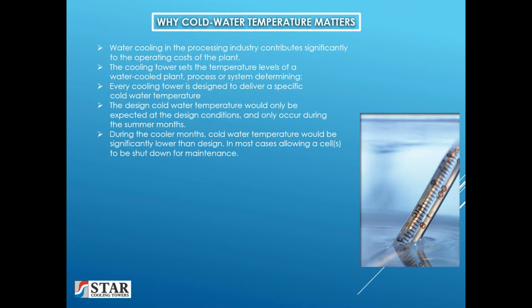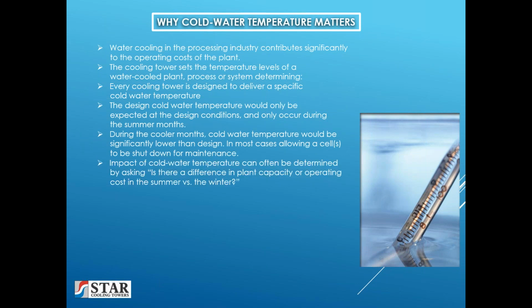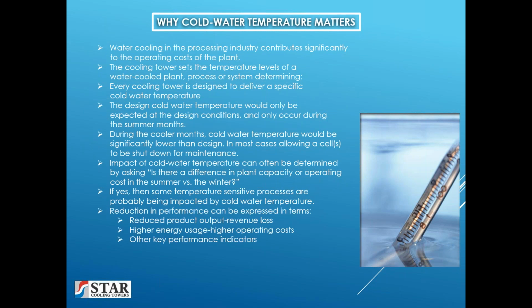During the cooler months, cold water temperature would be significantly lower than design, in most cases allowing a cell or cells to be shut down for maintenance. The impact of cold water temperature can be determined by asking, is there a difference in plant capacity or operating cost in the summer versus the winter? And if the answer is yes, then some temperature-sensitive processes are probably being impacted by cold water temperature. Any reduction in performance can be expressed in terms of reduced product output with revenue loss, or higher energy usage, increasing operating costs, or any other key performance indicators.